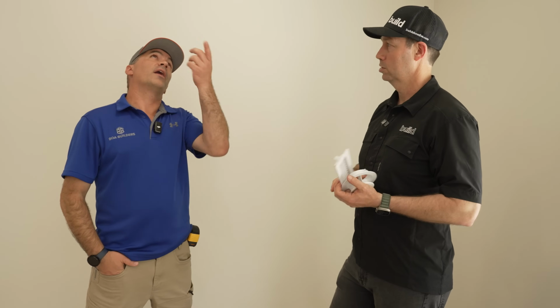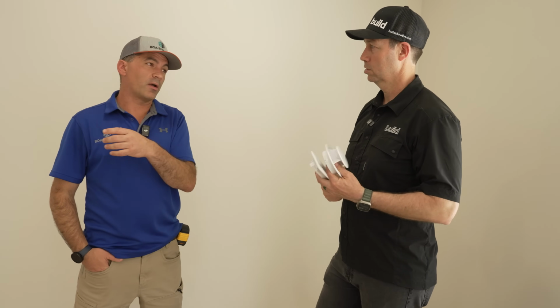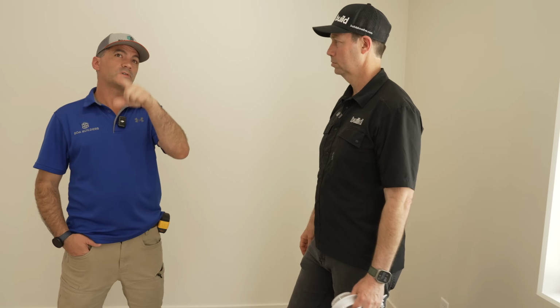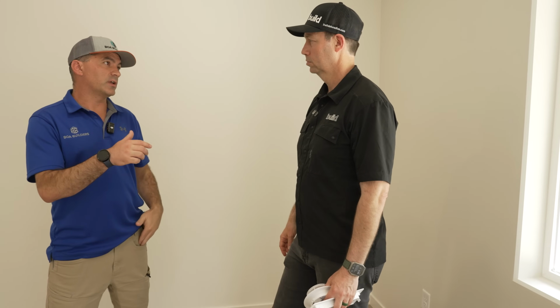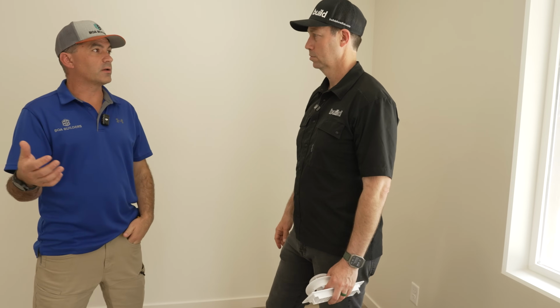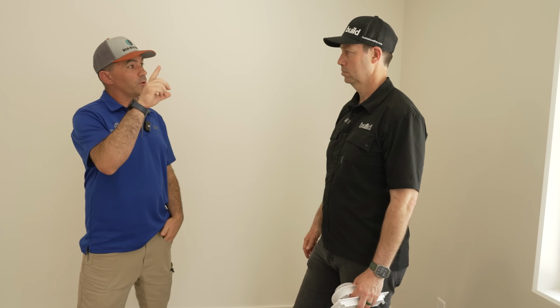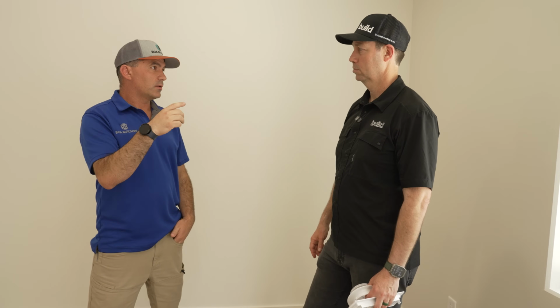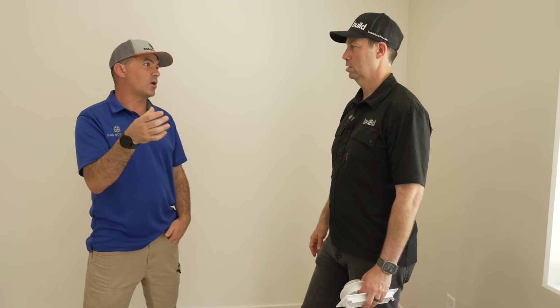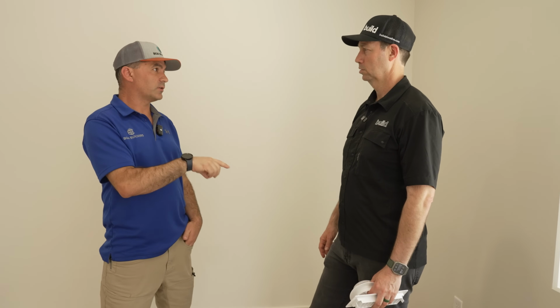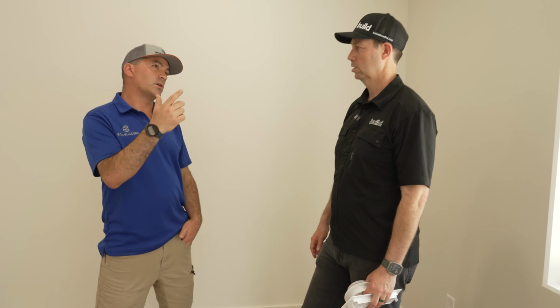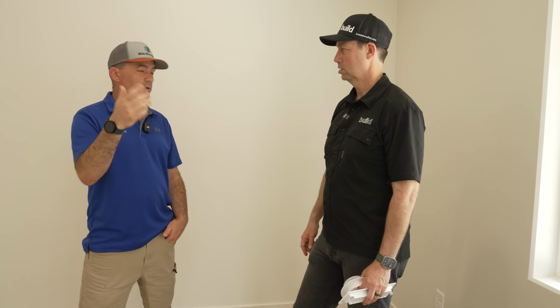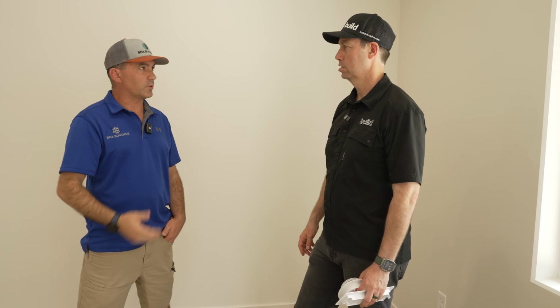Yep, and so at this stage, we'll come back in after it's fired up. We'll use a flow hood. They test every single one. We can put the actual CFM into the computer software of Rheia, and it spits out what the damper should be. So it might be a 1. Theoretically, if it's all correctly installed, they'd all be at a 0, and you'd get those CFM numbers. Gotcha. But if we need to tone one back, add one, they'll adjust all that, and now it's completely balanced.